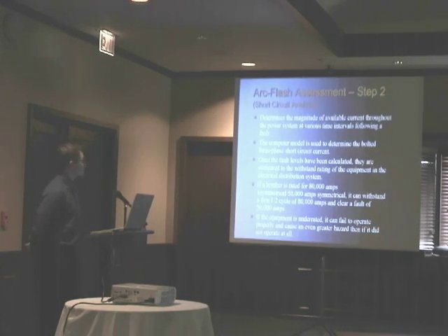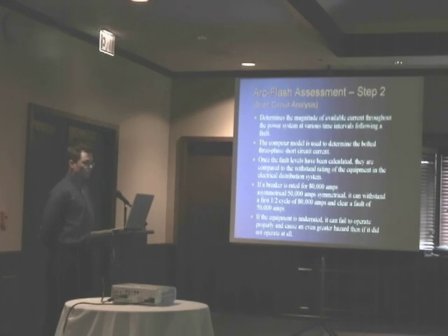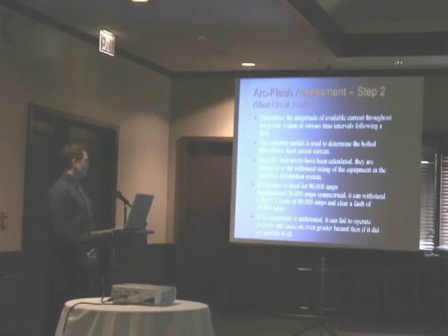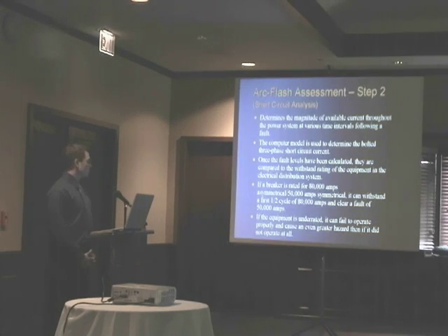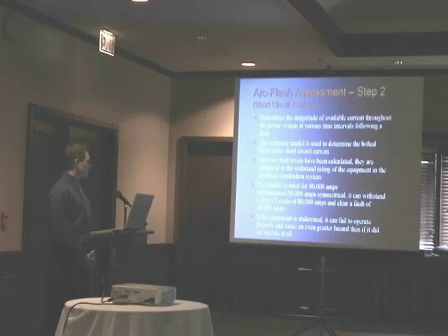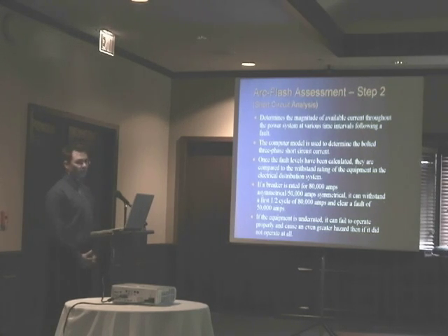The second step is short circuit analysis. This determines the magnitude of available fault current throughout the power system at various time intervals following a fault. The computer model is used to determine the bolted three-phase short circuit current. Once the fault levels have been calculated, they are compared to the withstand rating of the equipment in the electrical distribution system. If the breaker is rated at 80,000 amps asymmetrical, 50,000 amps symmetrical, it can withstand the first 1/2 cycle of 80,000 amps and a fault of 50,000 amps. If the equipment is underrated, it can fail to operate properly and cause an even greater hazard than if it did not operate at all.